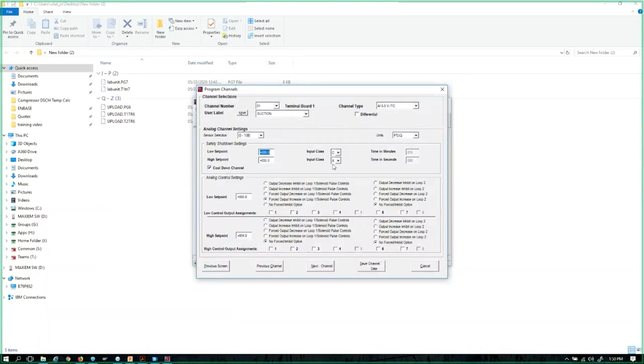And I'm going to keep my high kill as a class A. And I'm going to leave my low kill at 0 PSI and keep it as a class C. Now notice when it's a C, the time in minutes is grayed out right here, and it says 10 minutes. So that links back to the global timer for the class C timers on the first section that we covered. Also notice right here we have a cooldown channel and that we have a box checked for it.